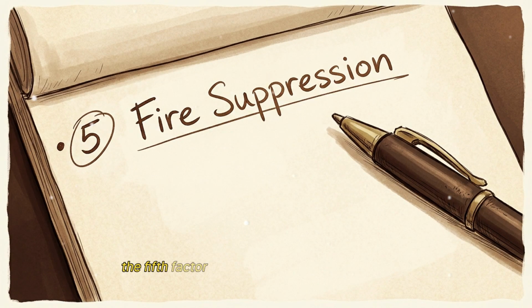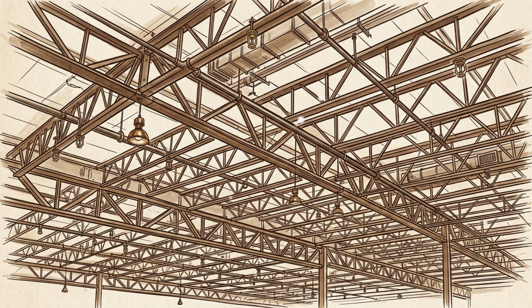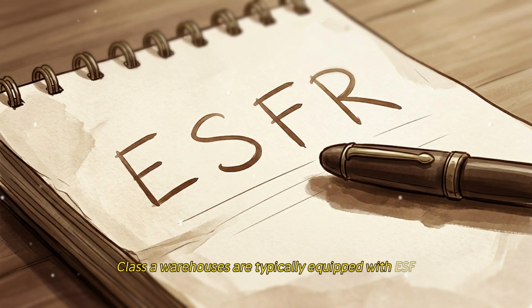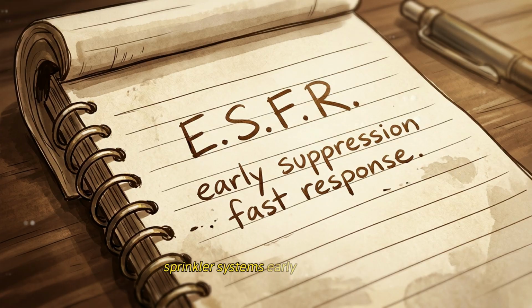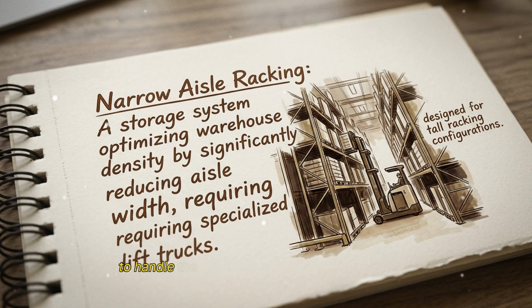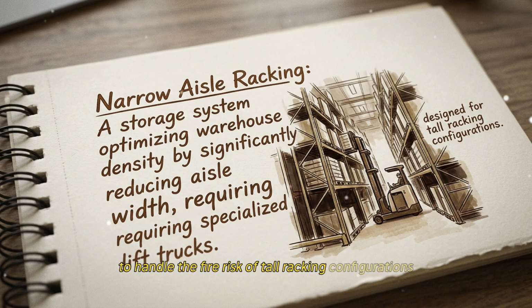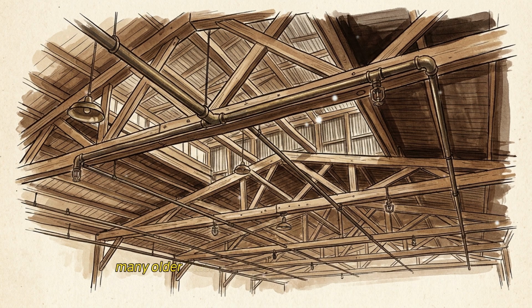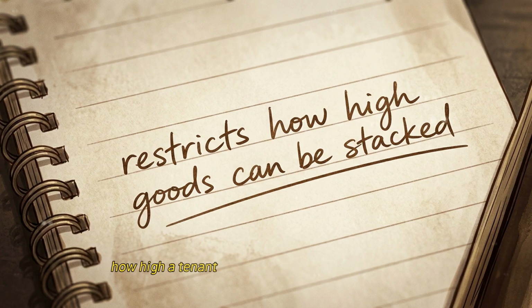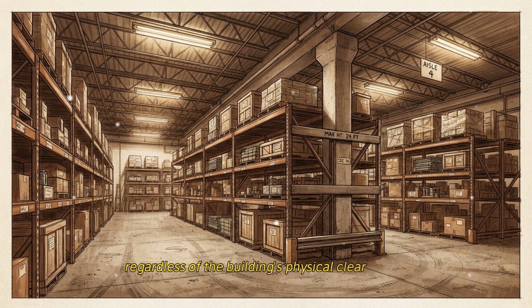The fifth factor, and an increasingly important one, is fire suppression. Modern Class A warehouses are typically equipped with ESFR sprinkler systems, early suppression fast response systems, designed specifically to handle the fire risk of tall racking configurations. Many older Class B buildings still operate with older, less capable sprinkler systems, which can restrict how high a tenant is legally permitted to stack goods, regardless of the building's physical clear height.